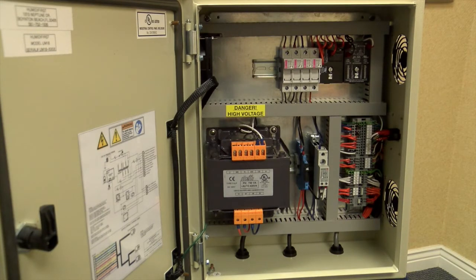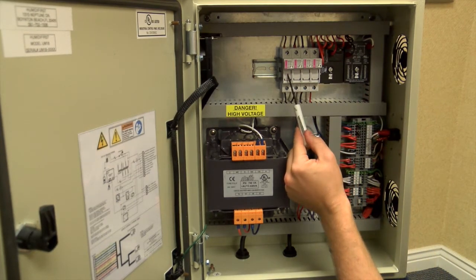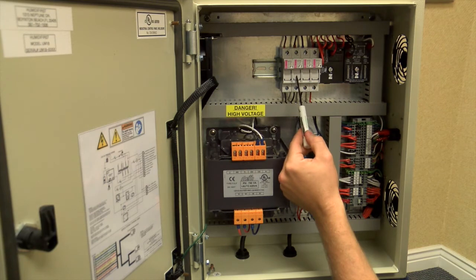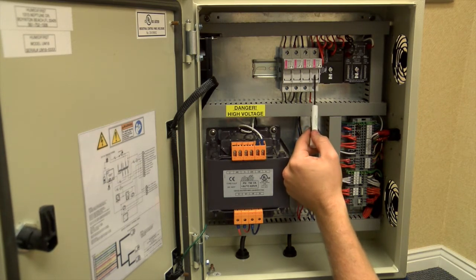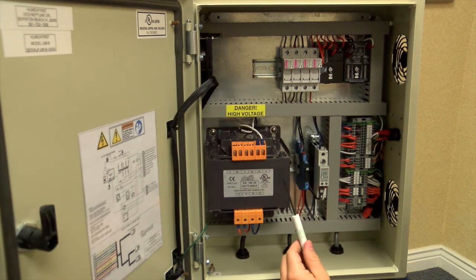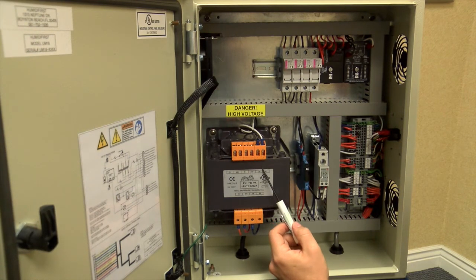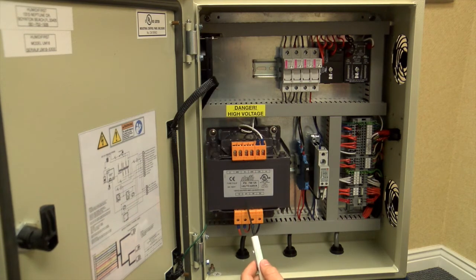We're now going to go over an overview of the internal circuitry. Right here is the F1 fuse. F1 is for your incoming power. F2 is going to be for your internal 120. F3 is going to be for your 48 volts that control your transducers. F4 is going to be your 24 volts that control your solenoid valve and float switch. Here is your transformer. It's wired at the 120 volts primary side and your secondary side 24 and 48 volts.